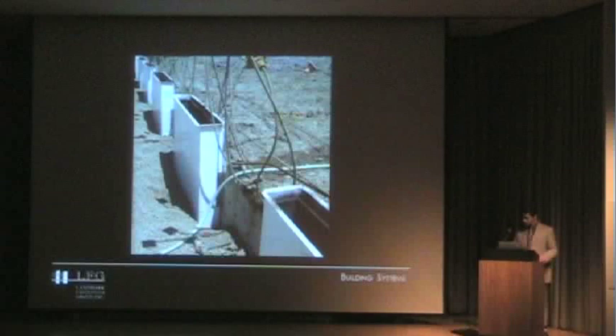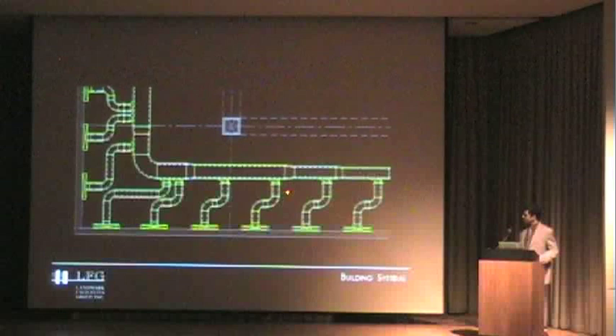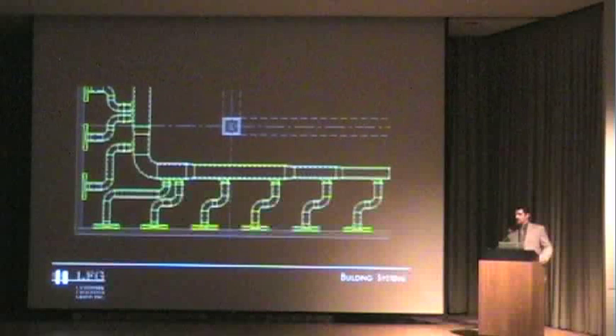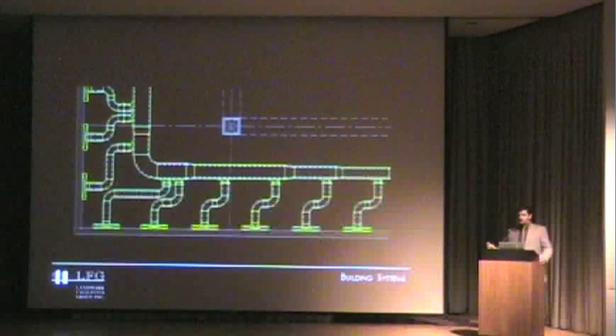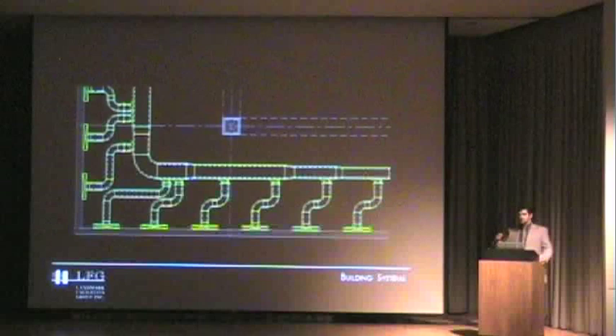In addition, each branch duct that feeds the perimeter has a balancing damper. But balancing dampers historically generate a great deal of noise, as they add resistance to the air. As they add resistance and close, you get a lot of air turbulence around them, which causes noise.